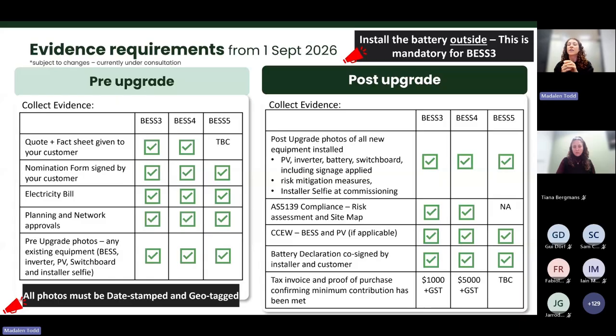Post-upgrade, the AS5139 requirements are needed, including the risk assessment of the battery for BESS 3 and BESS 4, and the site map of the battery confirming its location and clearance to exit windows. It should also include things like, if you installed a fire barrier, how tall and wide it is. We really recommend any risk mitigation measures you've installed be listed on the site map.